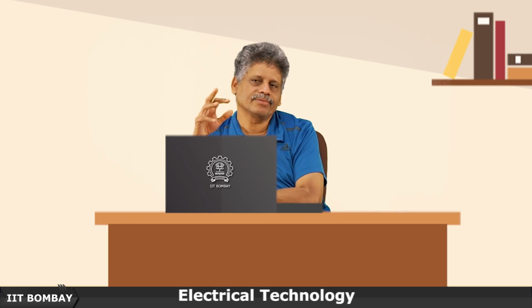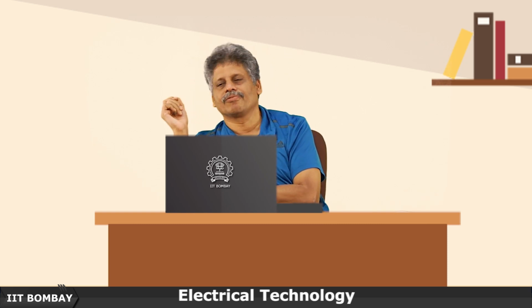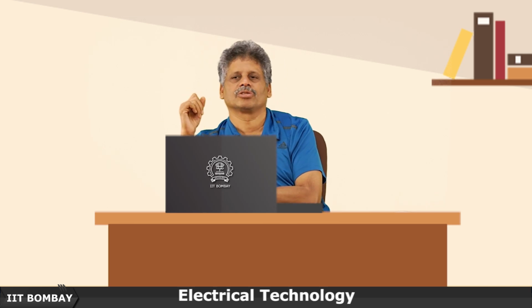We looked into that, and said that if the system is balanced, you can use a 2-wattmeter method for calculating power and power factor, using just 2 wattmeters instead of 3. But I also commented, what if one wattmeter has some error? So usually a 3-wattmeter approach would be good practice in instrumentation—try to instrument as much as possible, so that if there's any error in your instruments, you'll be able to figure it out.